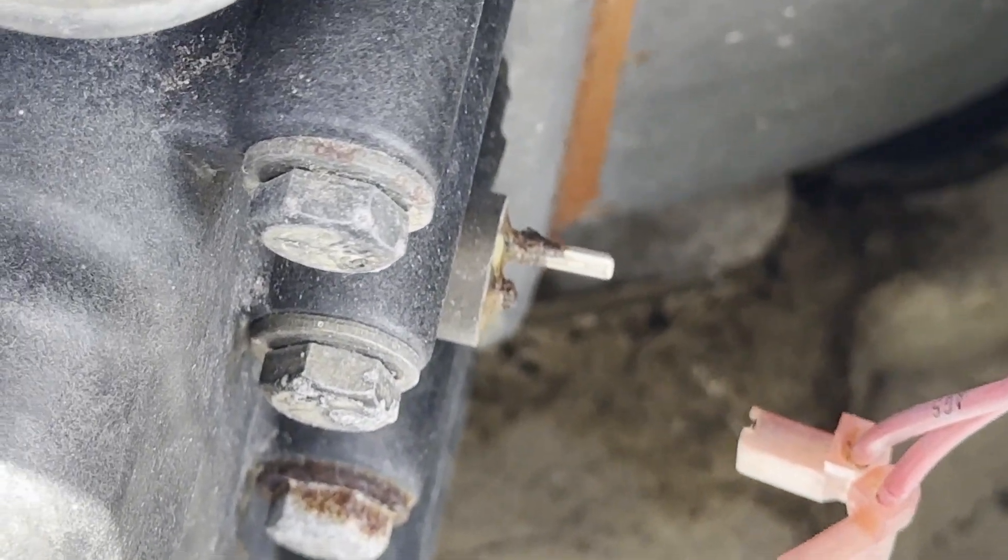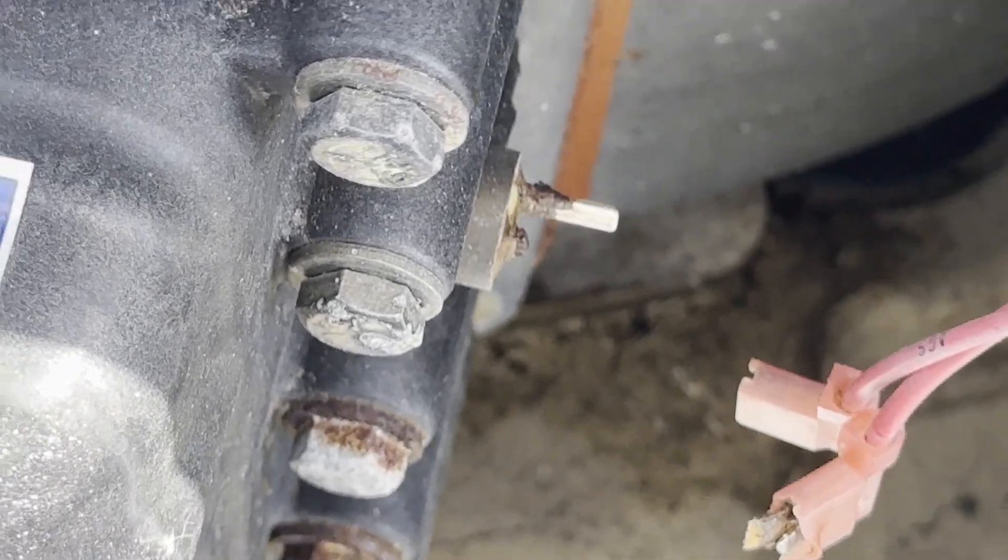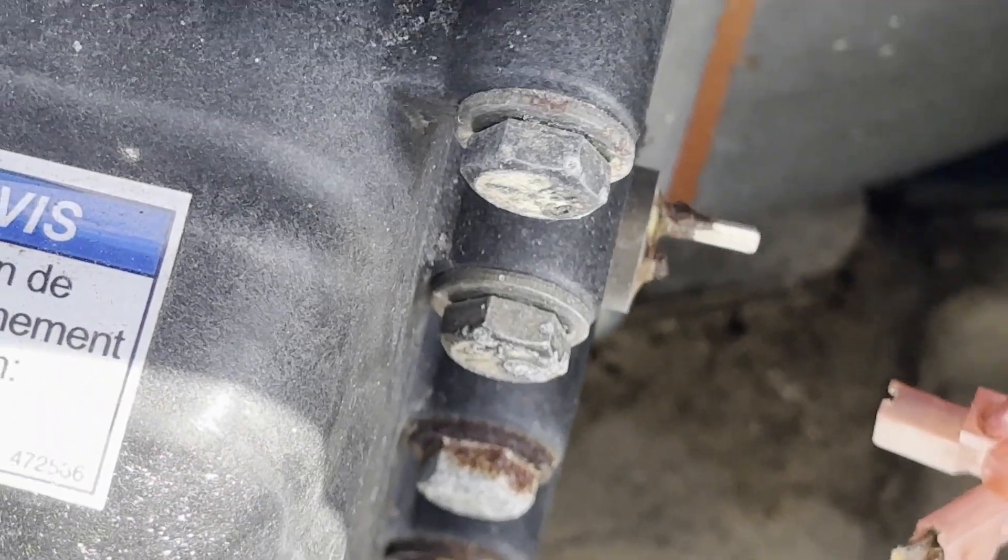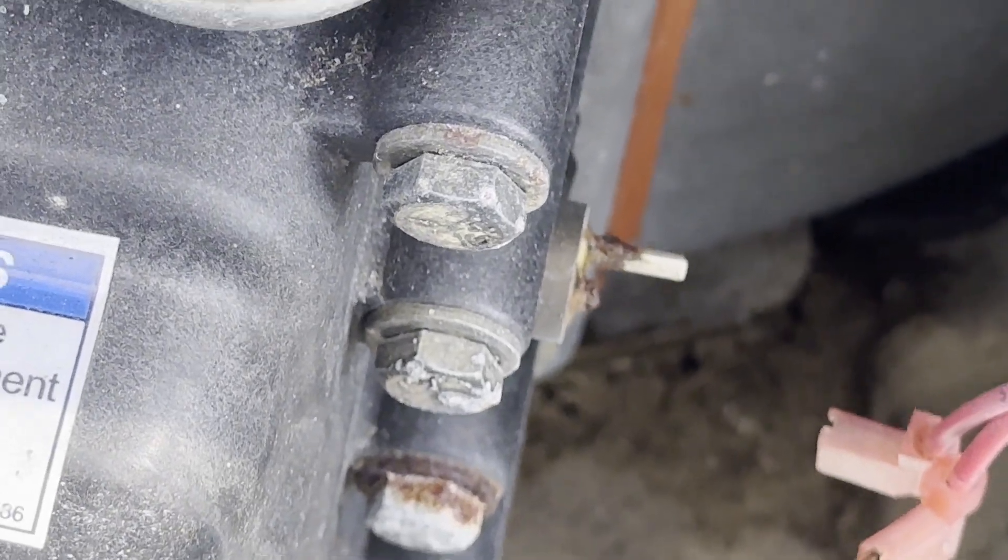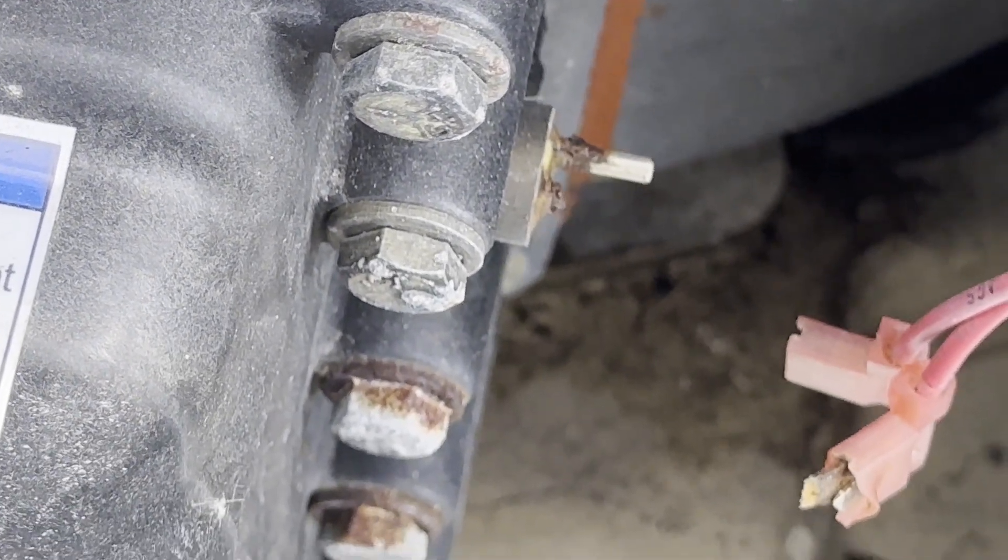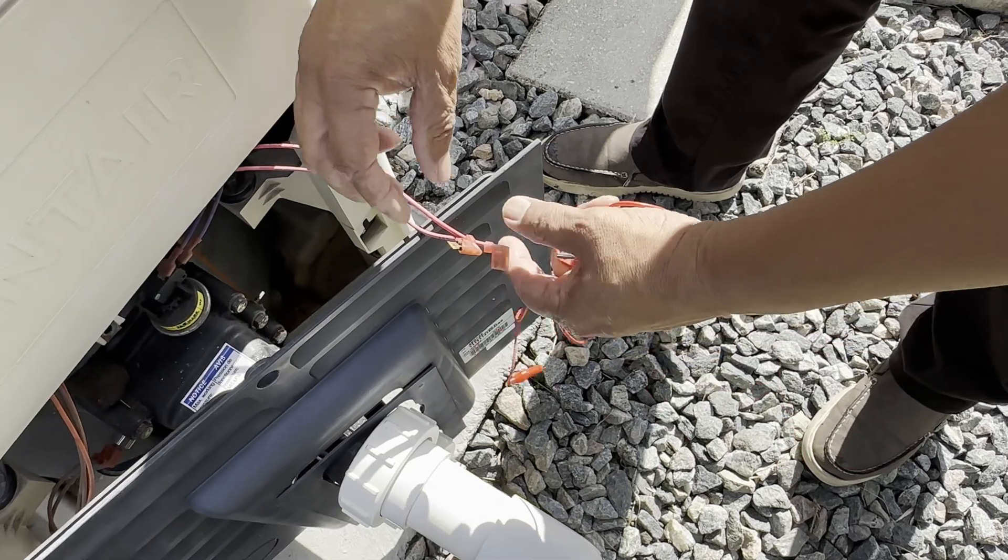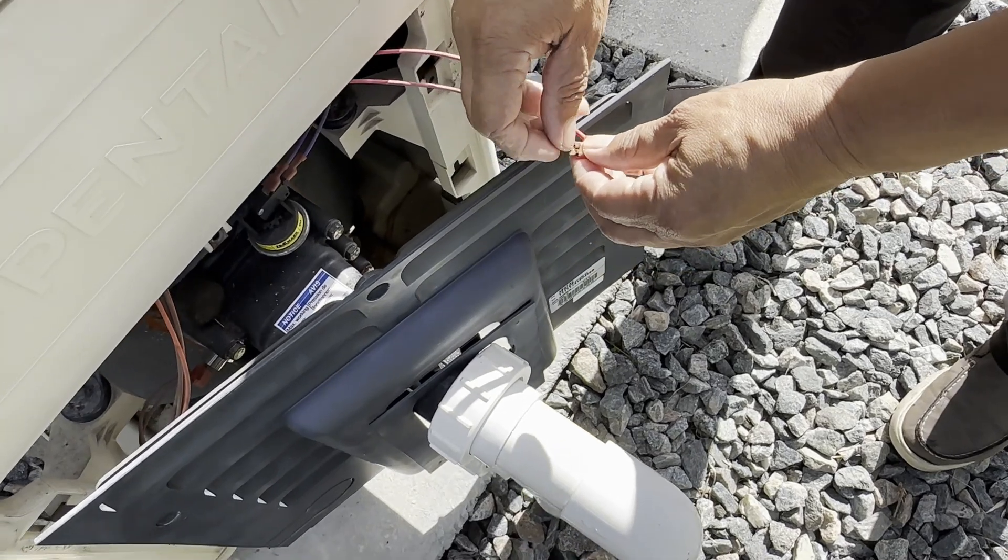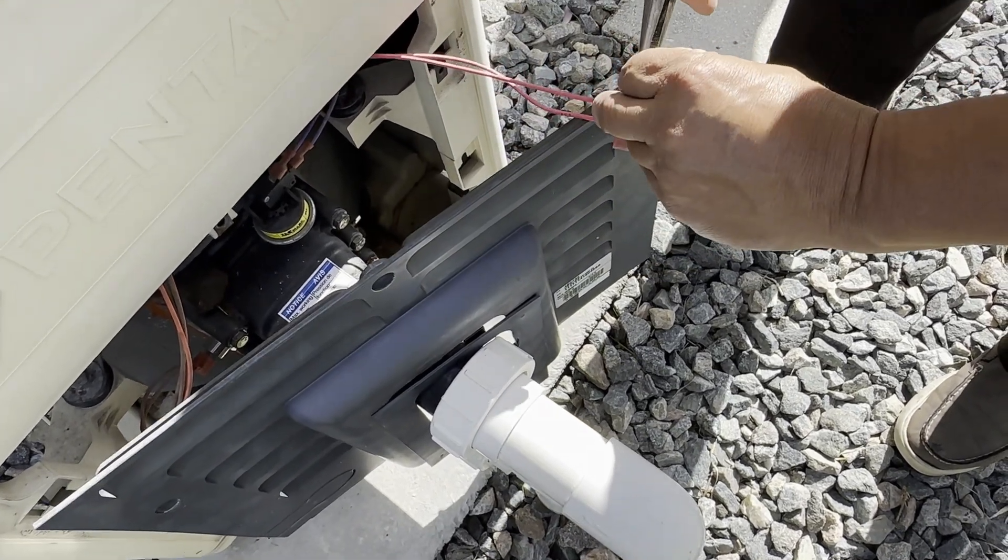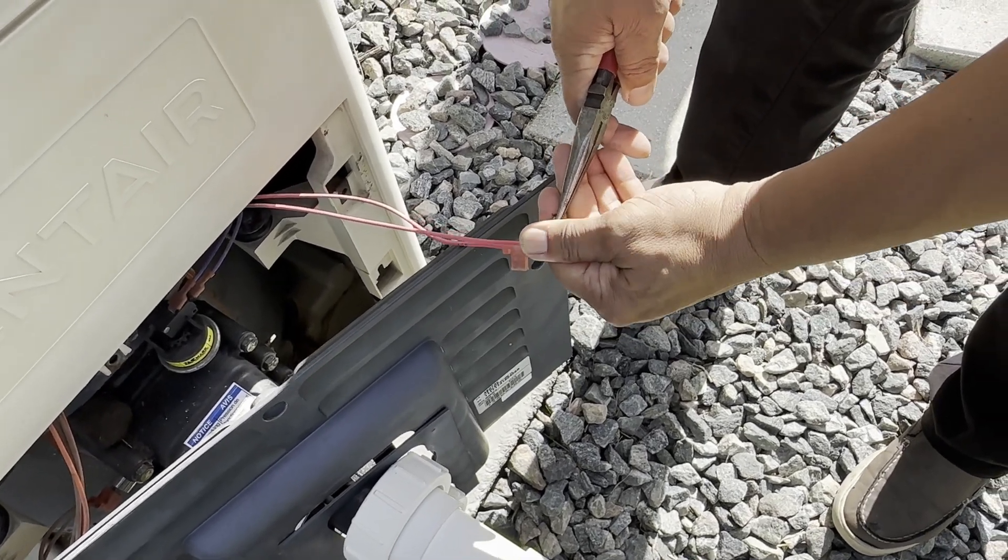So we're definitely going to have to change the autogas shutoff. Now, to see if that is the problem, what we can do is we can jump this. And we'll jump it. We'll try the heater again. And if it powers up and starts heating, then we know that that is the problem. So let's do that. We're going to get a jumper. We have a jumper here, just two alligator clips. And we're going to remove the piece. It's almost out. It's really corroded.